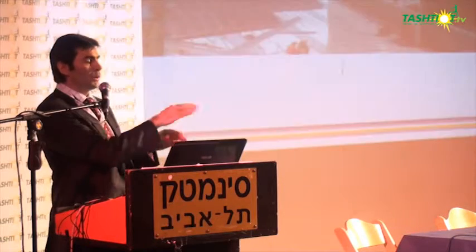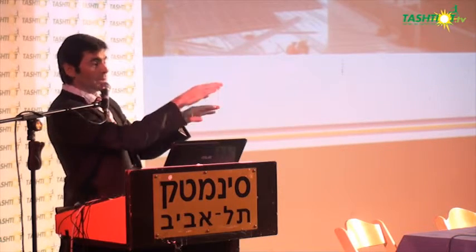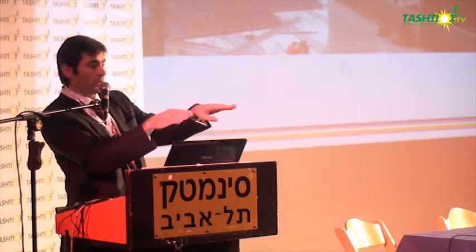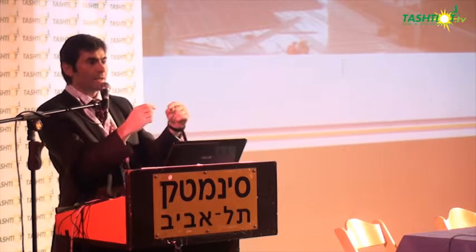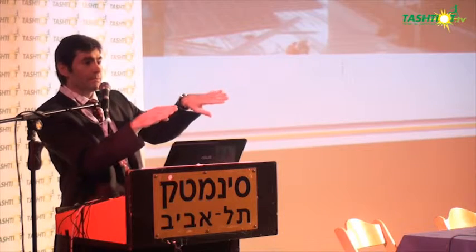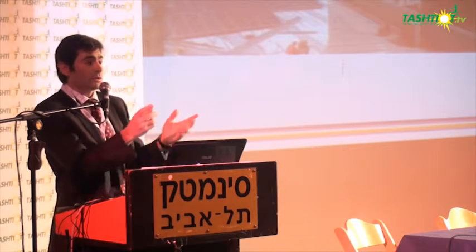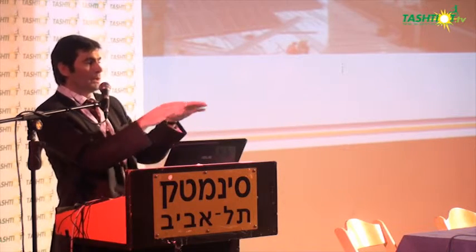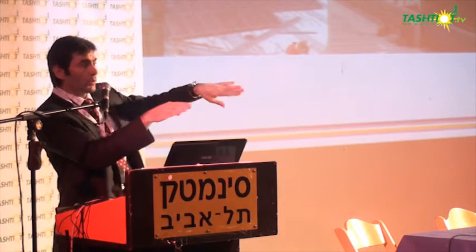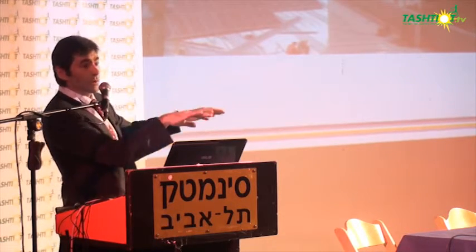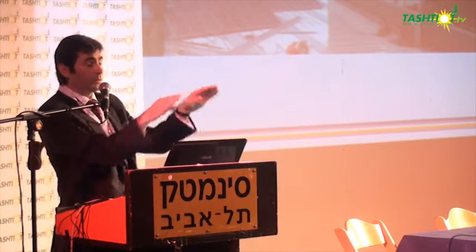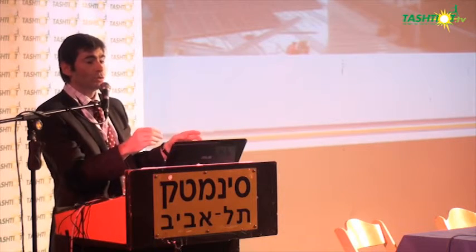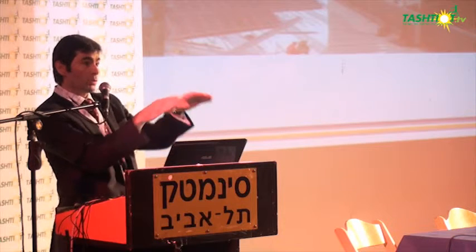When you're on a rooftop and you have one roof, some of them have 2 parts of the roof. One is to the south and the other one is to the north. If you connect both sides with the same inverter, since they are not in the same direction, the inverter is going to get crazy because it won't be able to find the maximum power point tracking. So it's a good idea, for example, if you have 4 slopes, to connect the 2 northern with the same inverter and the 2 southern with the same inverter. Or, for example, if you have 2 slopes and you have 50 kilowatts in total, you don't use just one inverter of 50. You use 2 inverters of 25, and each slope is with one of the inverters.